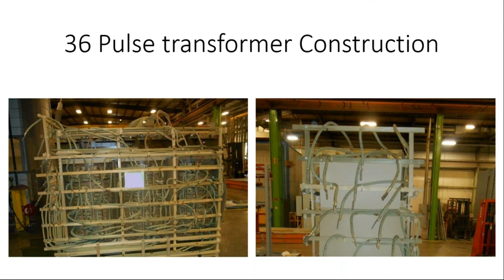So it's very critical to ensure the leads are identified properly and the crimp connections are made. The rating which the engineer designs for the extended portion is based on the line current of the delta, whereas the delta portion is designed for the phase current. So the design itself is a challenge, and then having all these connections made. Most of these windings are in different portions to keep short circuit forces minimum, so they're not all clubbed together. They are distributed over the full axial height of the transformer.